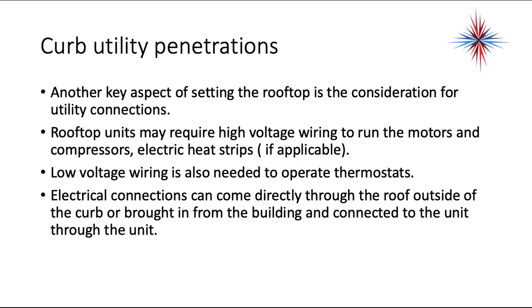Another key aspect of setting the rooftop is the consideration for utility connections. Rooftop units may require high voltage wiring to run the motors and compressors and electric heat strips. Low voltage wiring is also needed to operate the thermostats. Electrical connections can come directly through the roof outside of the curb, or be brought in from the building and connected to the unit through the unit.